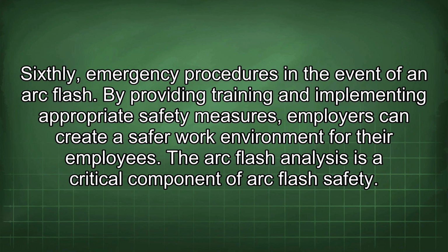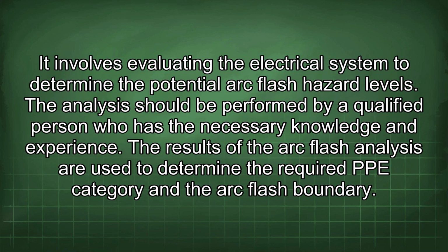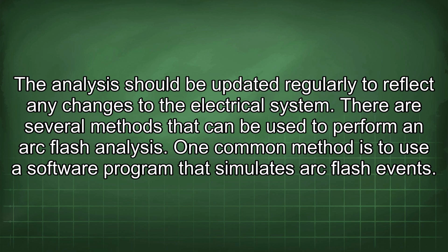The arc flash analysis is a critical component of arc flash safety. It involves evaluating the electrical system to determine the potential arc flash hazard levels. The analysis should be performed by a qualified person who has the necessary knowledge and experience. The results of the arc flash analysis are used to determine the required PPE category and the arc flash boundary. The analysis should be updated regularly to reflect any changes to the electrical system.